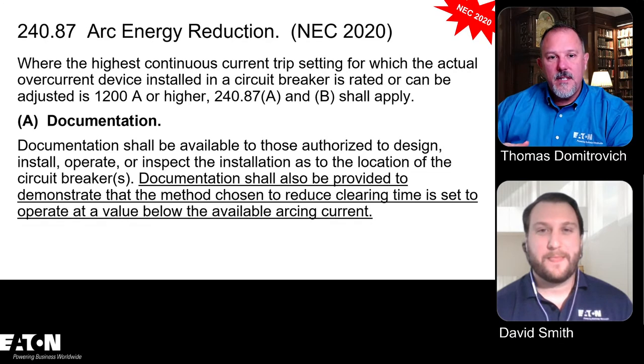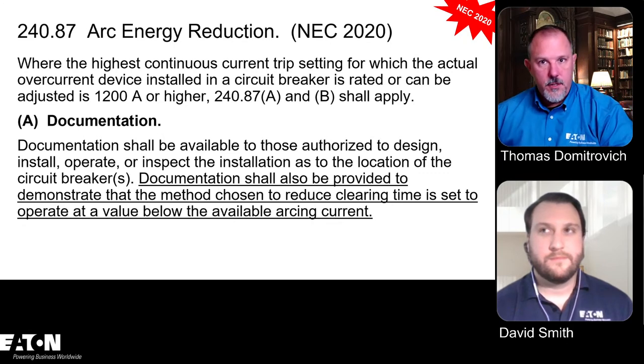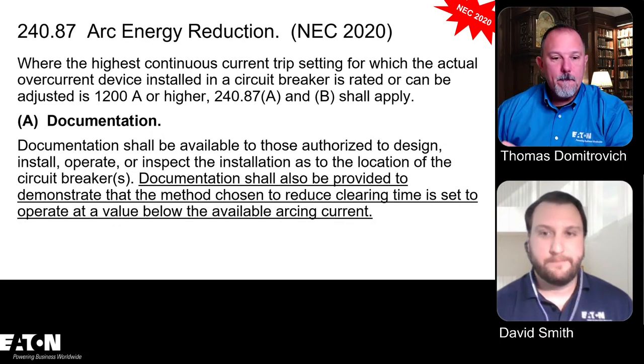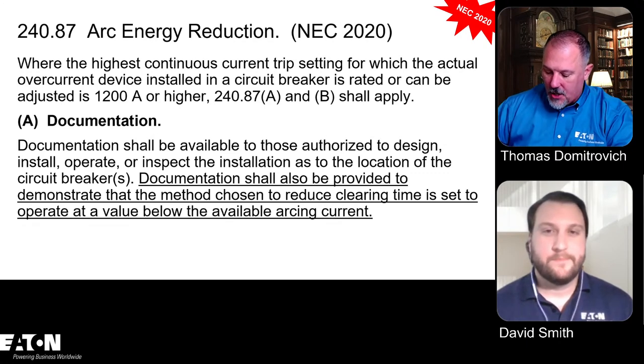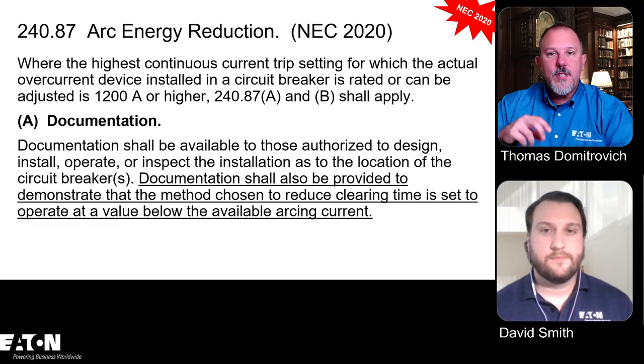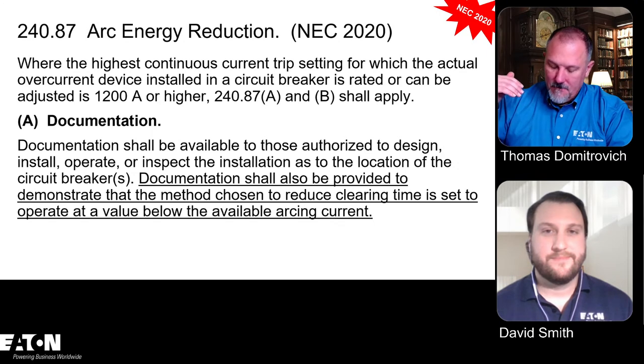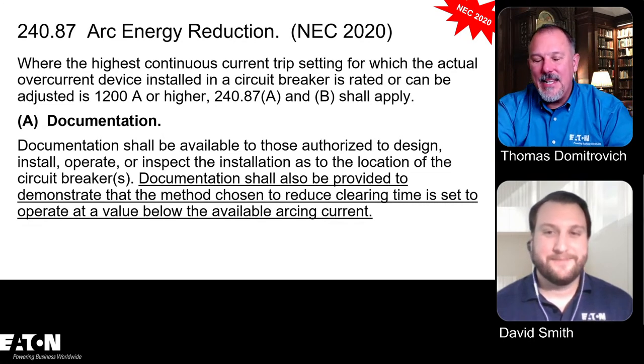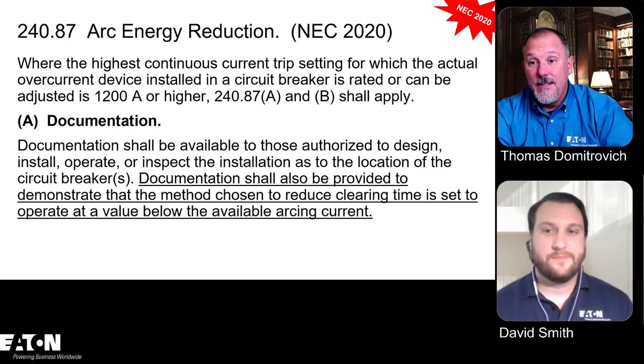So fault current available. Now, this isn't available arcing current. This is available fault current. The 2020 code created the definition of available fault current. It was 70E that created the term first, and then we followed suit in the code. And this is in Article 100? It's in Article 100, and it says the largest amount of current capable of being delivered at a point, blah, blah, blah. So when you say available fault current, it's the largest amount of fault current that can be delivered at that point. When I say available arcing current, it's real easy to sit down and go, well, that's the maximum amount of arcing current that can be delivered to that point. But that would not technically be the right thing to do. That's right. And I was thinking we were going to clean this up in the 2023 cycle, and we really didn't. And you know what?